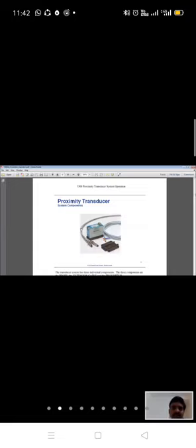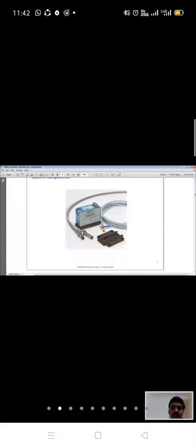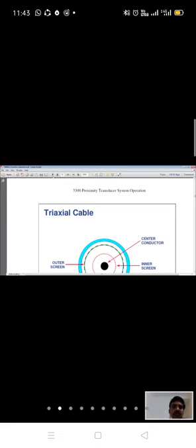And this is how the probe looks like. This is the probe, this is the cable, this is the proximeter, and this is the extension cable. Our flux will be generated here only. The extension cable is a special cable. Why we use a special cable here is we are generating a radio frequency signal and it is being transmitted up to the end of the probe.